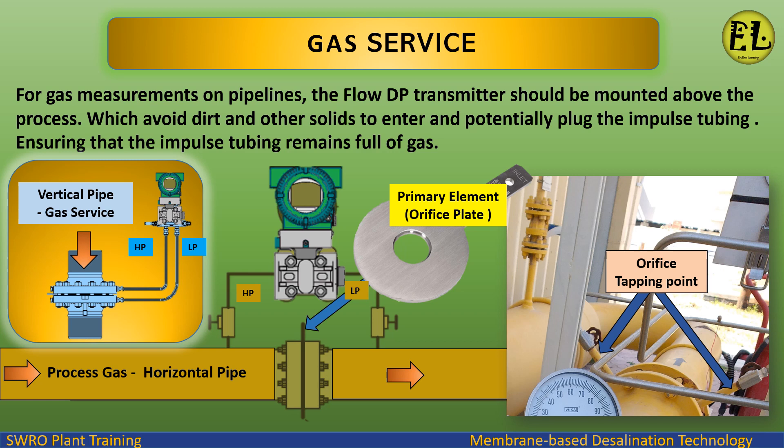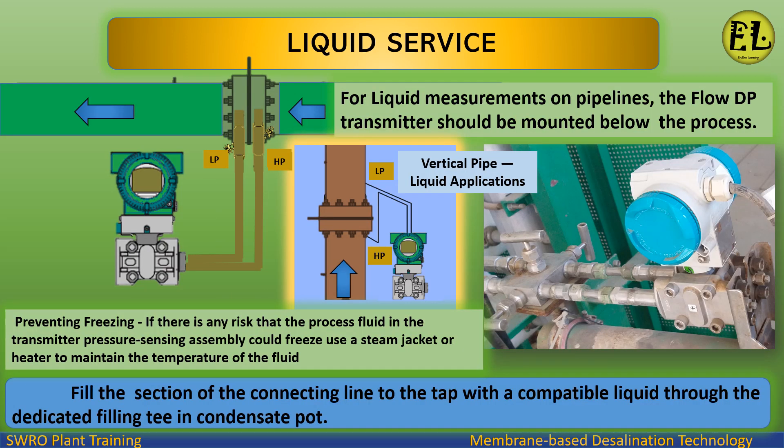For liquid service, for liquid measurements on pipelines, the flow DP transmitter should be mounted below the process. Fill the section of the connecting line to the tap with a compatible liquid through the dedicated filling tee in the condensate pot. To prevent freezing, if there is any risk that the process fluid in the transmitter pressure sensing assembly could freeze, use a steam jacket or heater to maintain the temperature of the fluid. DP flow meter installation for horizontal and vertical pipelines are shown.